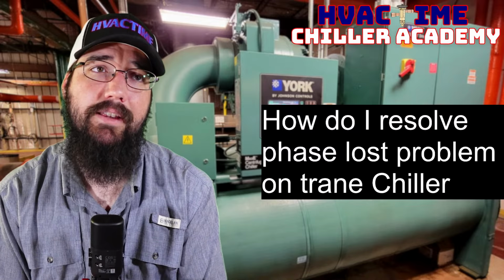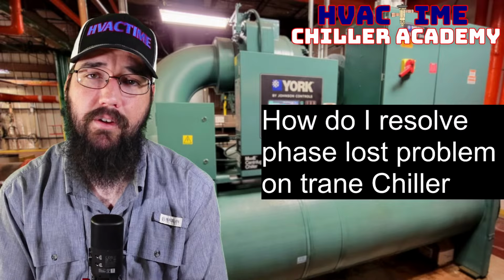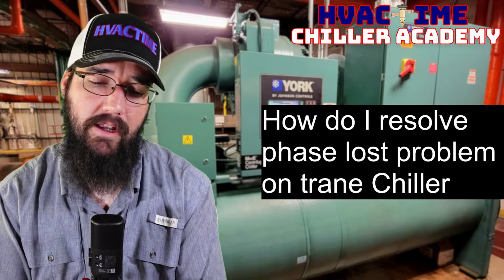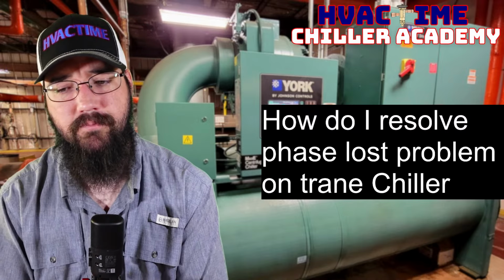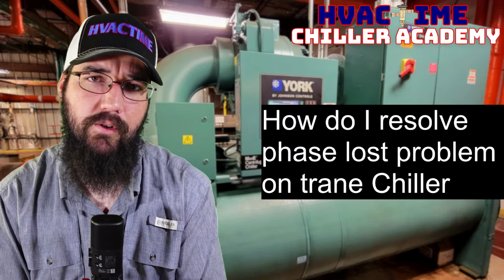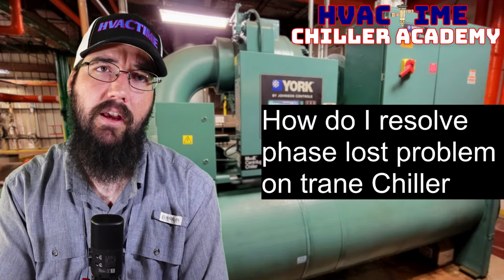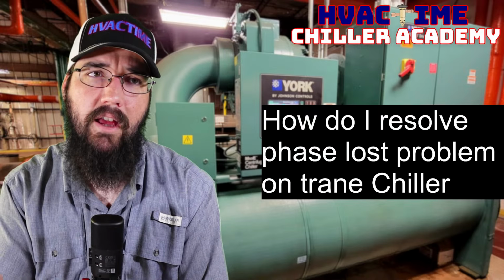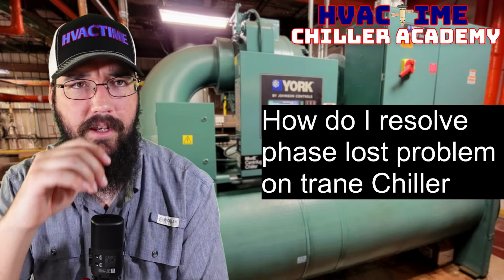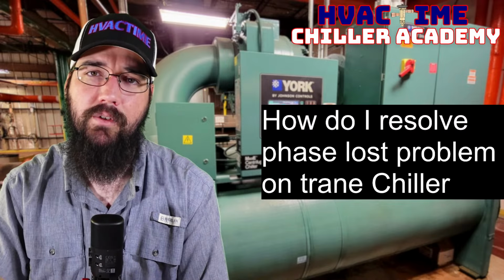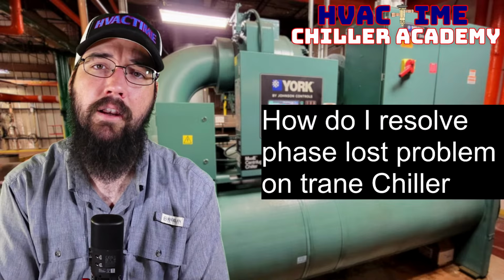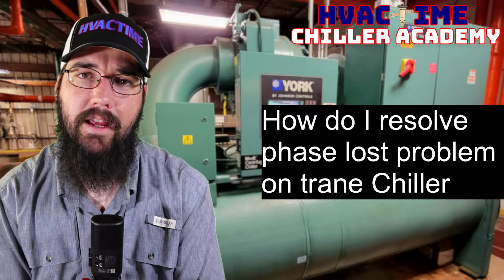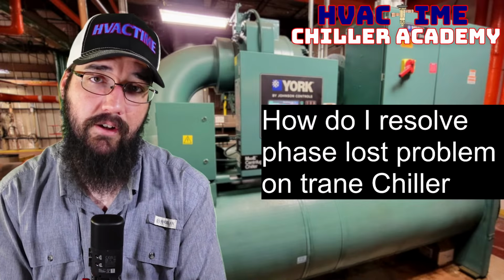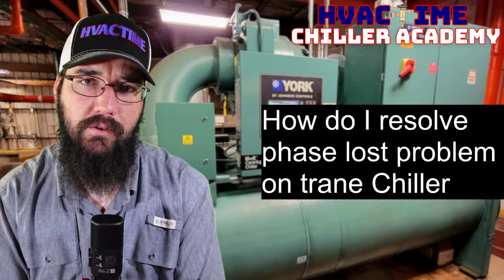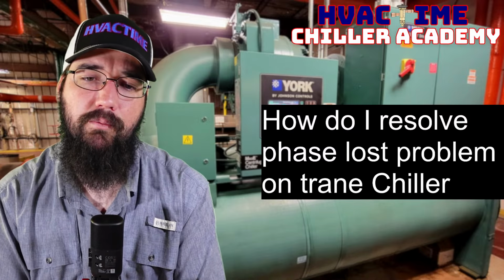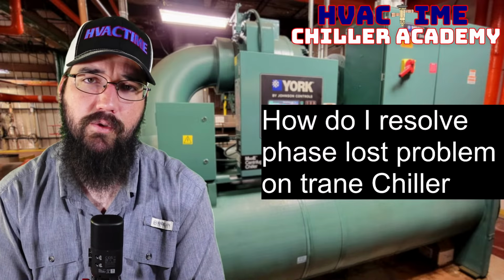So I've had that where the compressor stator was having trouble, had a weak side of the winding. When the compressor went to turn on, it was causing a heavy drawdown on the input side. Basically the input side would go unbalanced as soon as the compressor would try to engage, and it ended up being an issue with the stator itself. Change the compressor out, problem went away, right? So those can be really tricky to troubleshoot.